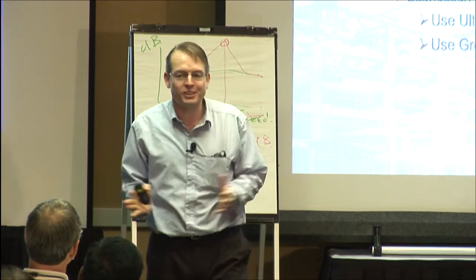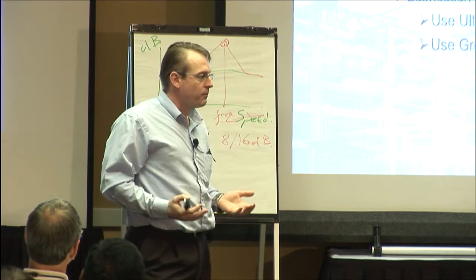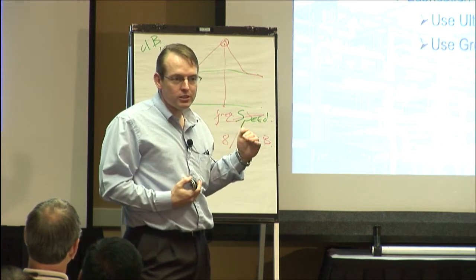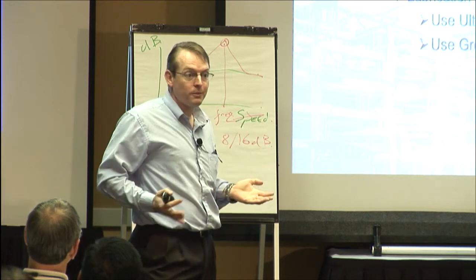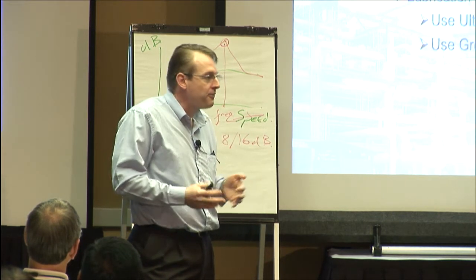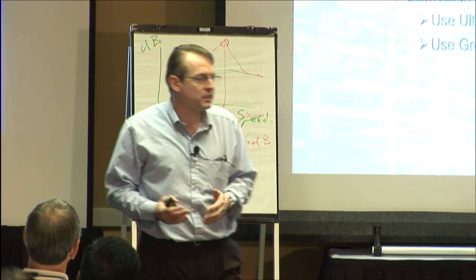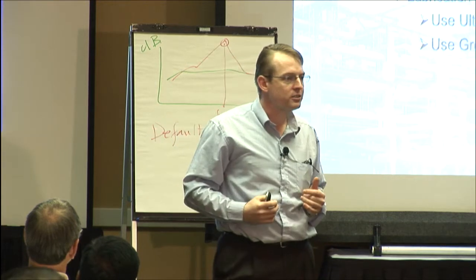Okay, in all seriousness, if the dBs don't go down, you stop. If the dBs go down, what do you do? Give it some more grease. dBs stop, what do you do? You stop, right? Pretty simple. We don't have to get very complicated, do we? Do we have to have a complicated DMS with all these extra curves depending on what speed we're running at and anything else?